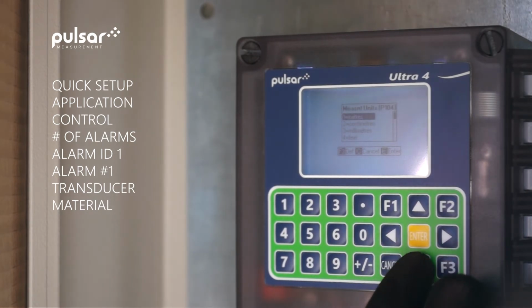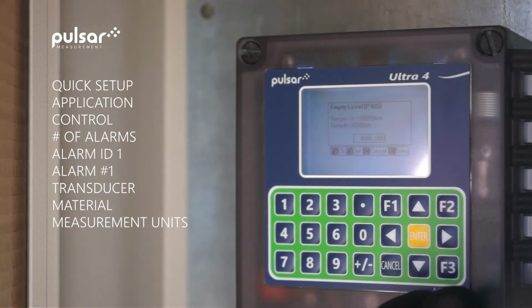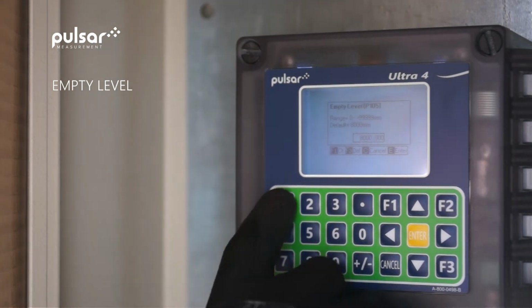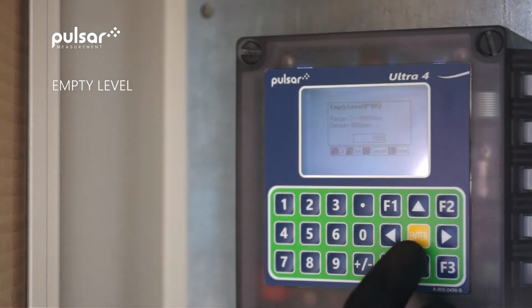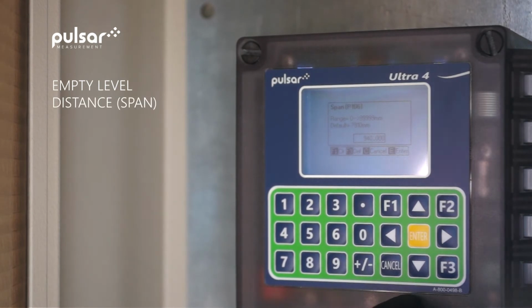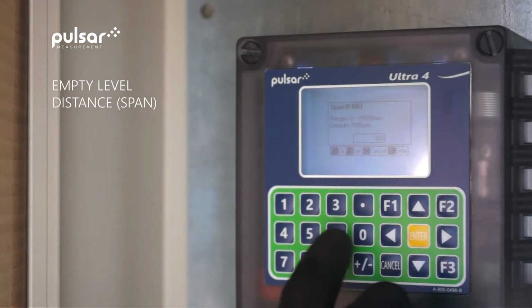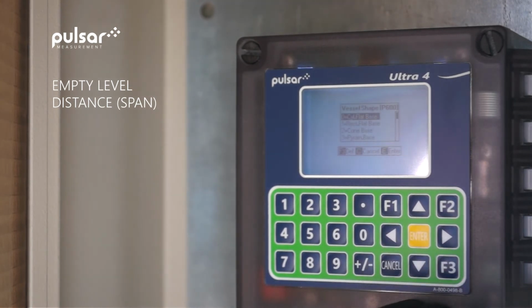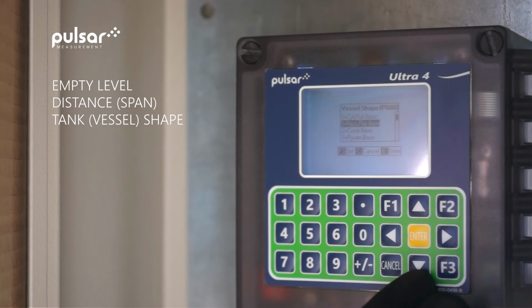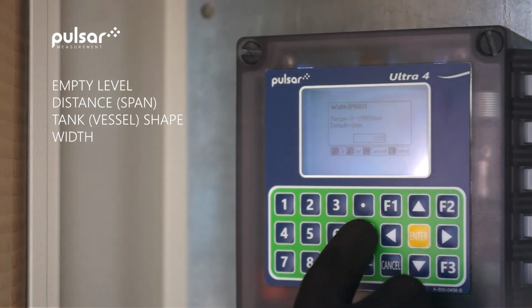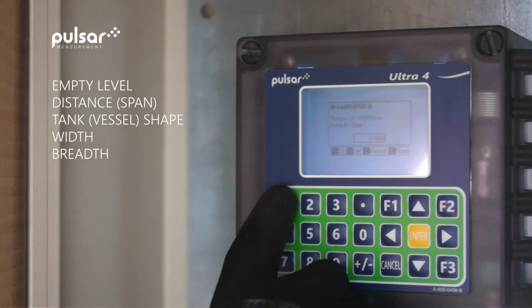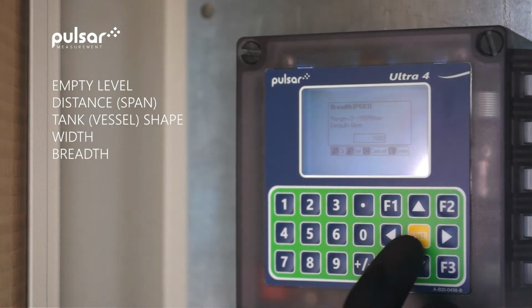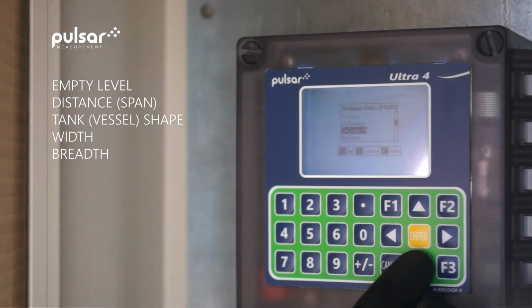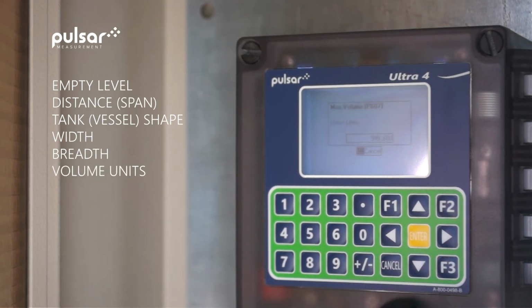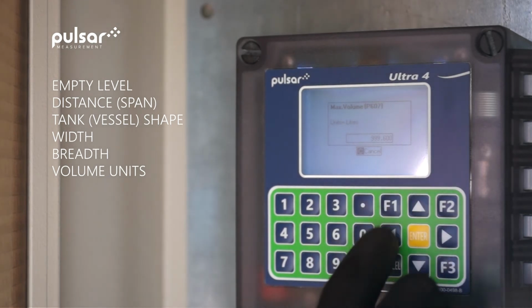Our measurement units are millimeters. The empty level 1030 millimeters. And our span is 833 millimeters. Our vessel shape is a rectangular flat base. The width 1200. The breadth 1000. And we'll be measuring volume in litres. This is the indication of the maximum volume.